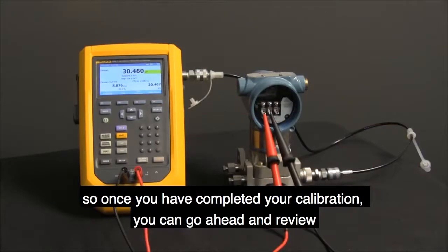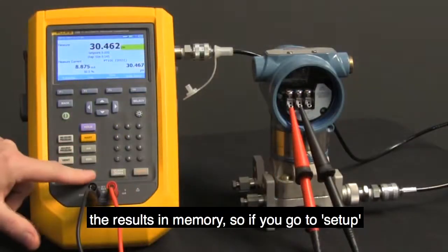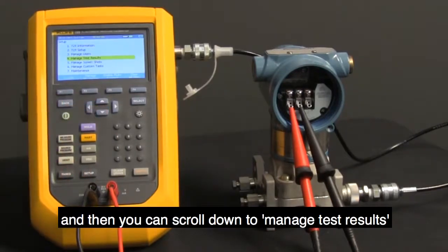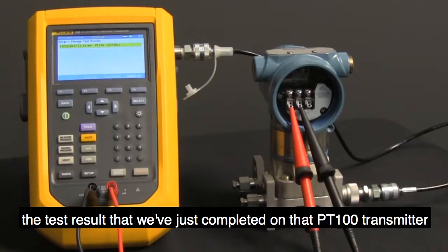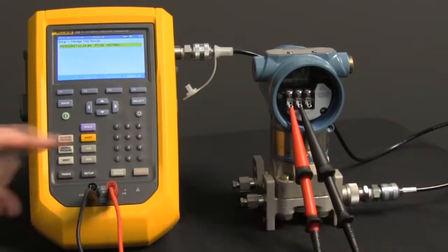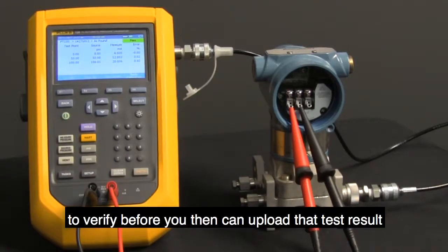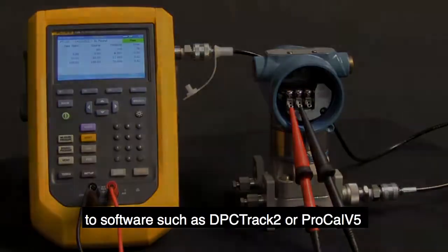So once you have completed your calibration, you can go ahead and review the results in memory. So if you go to Setup and then you can scroll down to Manage Test Results, press Enter. Now you can see the task, the test result that we've just completed on that PT100 transmitter. If you press Enter here, you can look at the actual test results to verify before you then can upload that test result to software such as DPC Track 2 or ProCal V5.